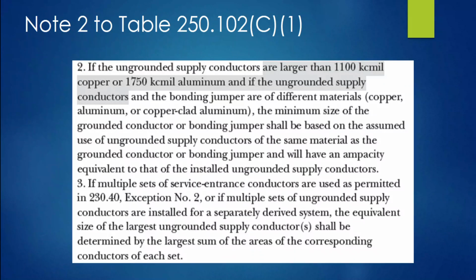All right, note 2 is a unique one here, and we're only going to deal with one aspect of it, because I captured both note 2 and 3. We're really just looking at note 2. The important part of this says, look, if the ungrounded supply conductors are larger than 1100 kcmil copper or 1750 aluminum, and, now that's an important "and," if the ungrounded supply conductors and the bonding jumpers are of a different material, copper, aluminum, or copper-clad aluminum, different than what you're using as the bonding jumper, then the minimum size of the grounded conductor or the bonding jumper shall be based on the assumed use of ungrounded supply conductors of the same material as the grounded conductor or bonding jumper, and will have an ampacity equivalent to that of the installed ungrounded supply conductors.